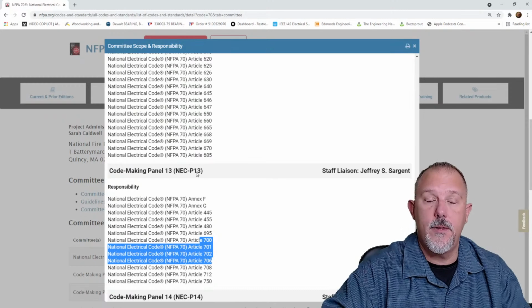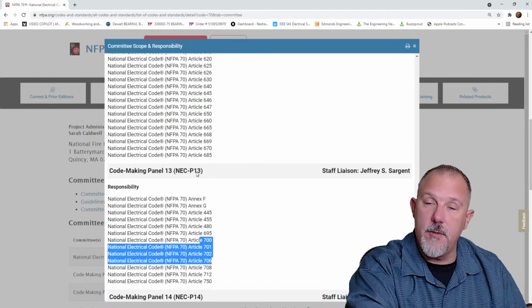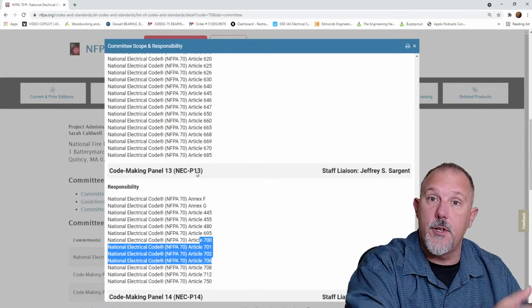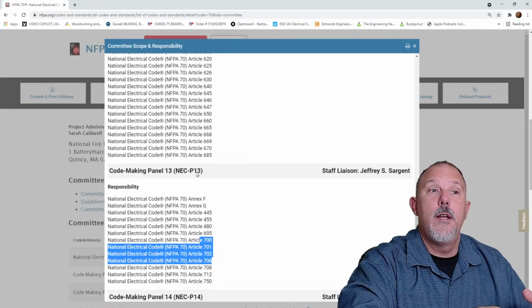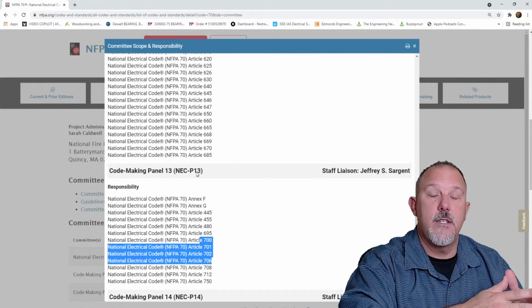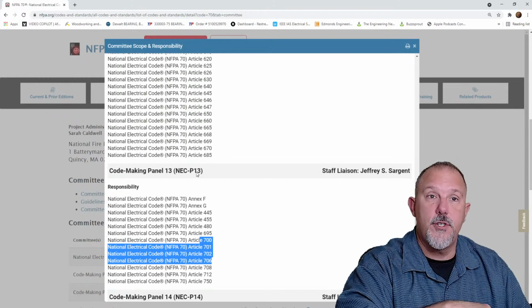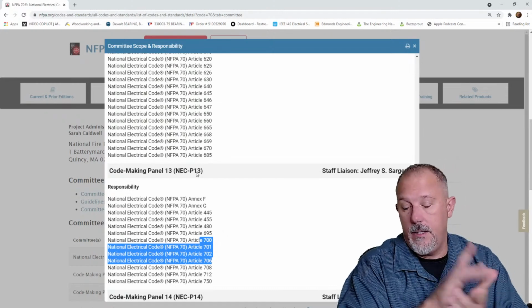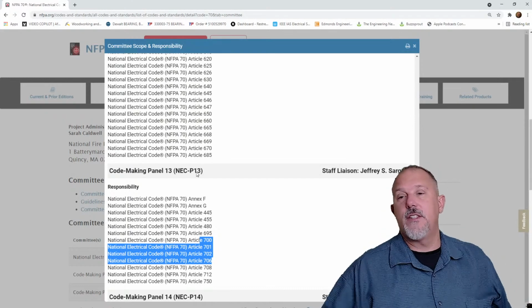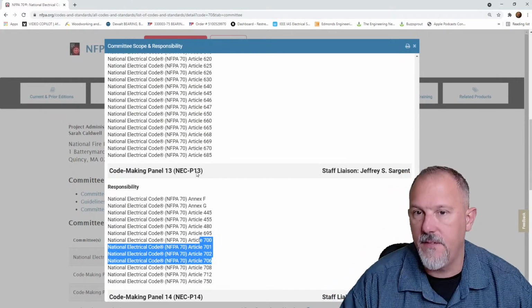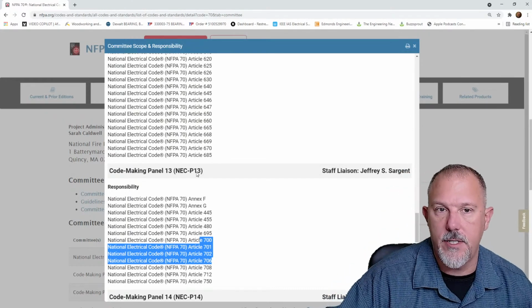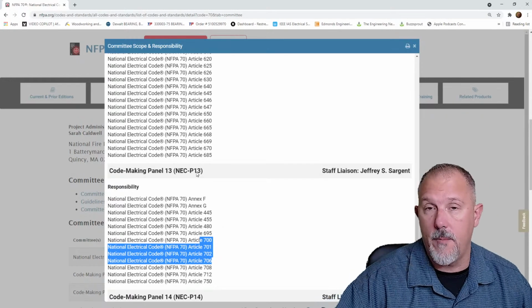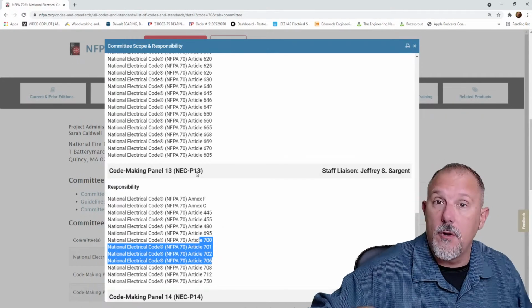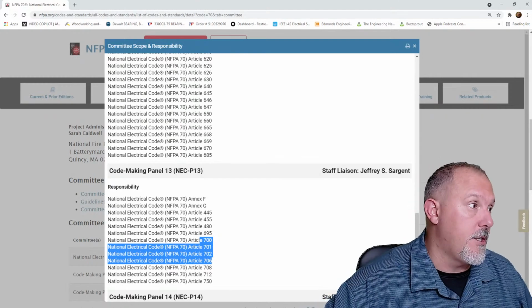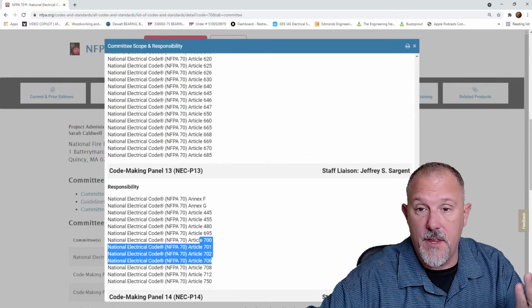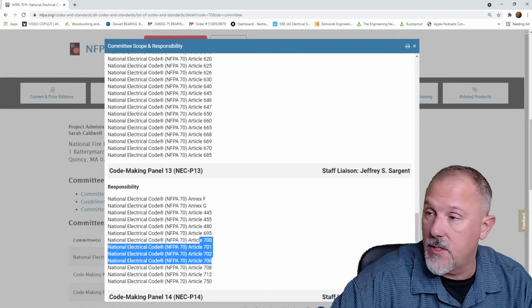Now the 2023 cycle is looking at selective coordination requirements for the normal side. Remember, and I think that's in 240 for feeders. I don't know. I'm on the fence on that one, Ryan. I am really on the fence on that one. The only reason I like it in 700, 701, 708, and wherever the requirement is because that's where you're looking anyway for the requirement for selective coordination. So anyhow, that's just my thought. I don't know. Take it for what it's worth.